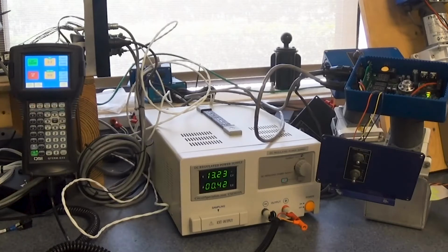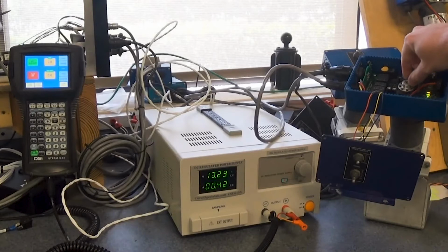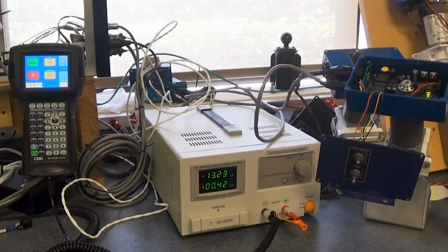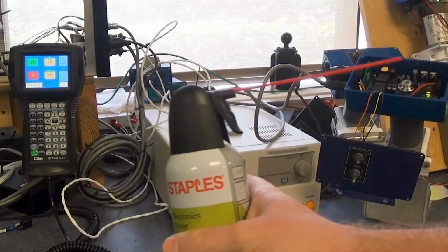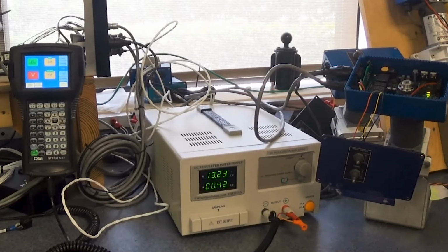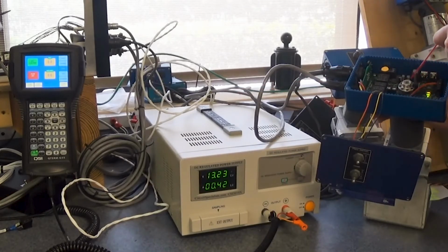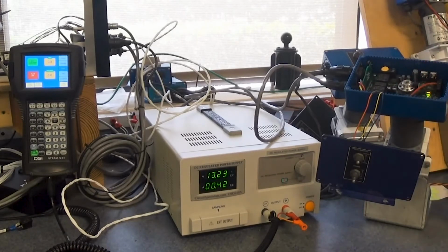Well, what happened here is this chopper wheel that's found inside the FMI pump right here has gotten some dirt on the lens. So how can we resolve this? Well, with a little bit of compressed air, like you could find in a keyboard cleaner, you just apply to the sensor. And now we have actually cleaned up the sensor.